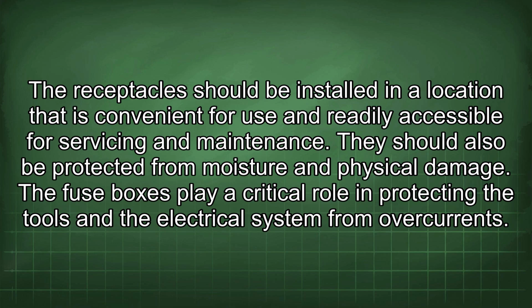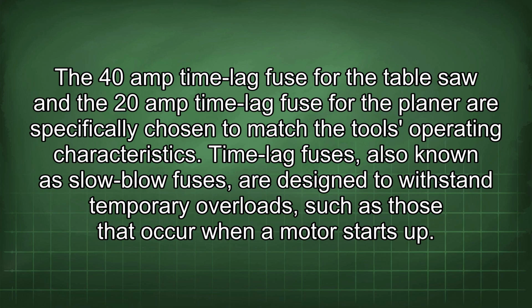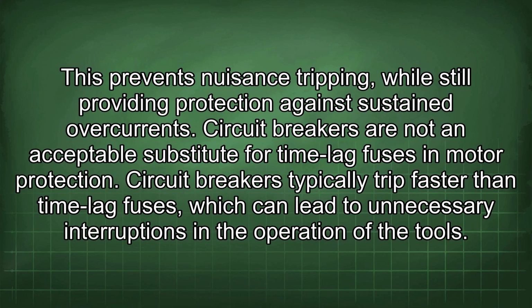The fuse boxes play a critical role in protecting the tools and the electrical system from overcurrents. The 40 amp time lag fuse for the table saw and the 20 amp time lag fuse for the planer are specifically chosen to match the tool's operating characteristics. Time lag fuses, also known as slow blow fuses, are designed to withstand temporary overloads, such as those that occur when a motor starts up. This prevents nuisance tripping while still providing protection against sustained overcurrents. Circuit breakers are not an acceptable substitute for time lag fuses in motor protection.